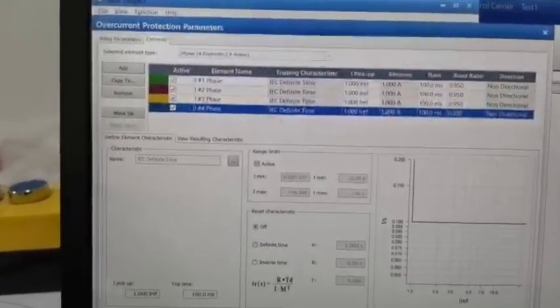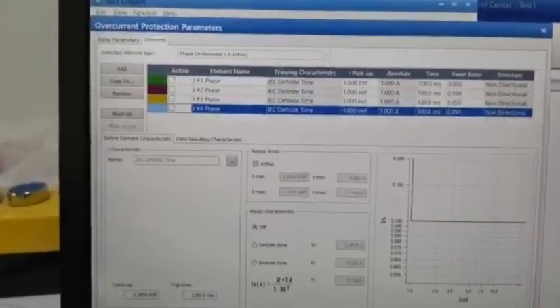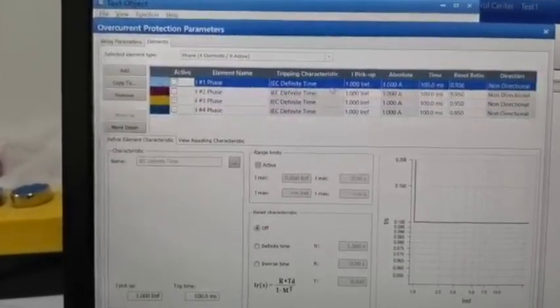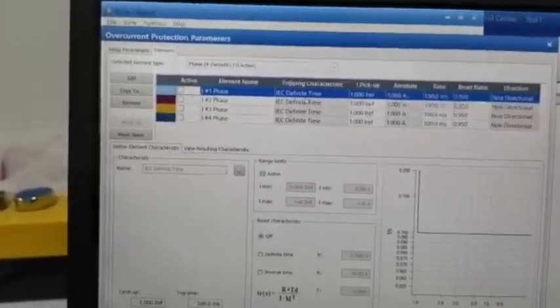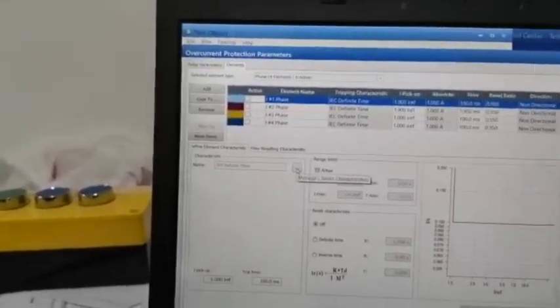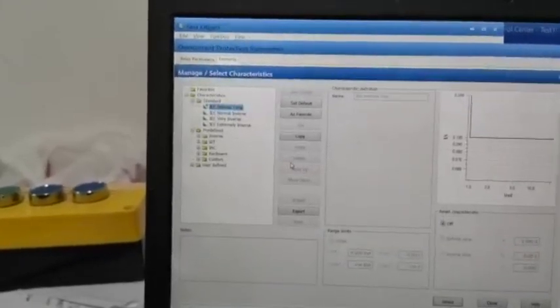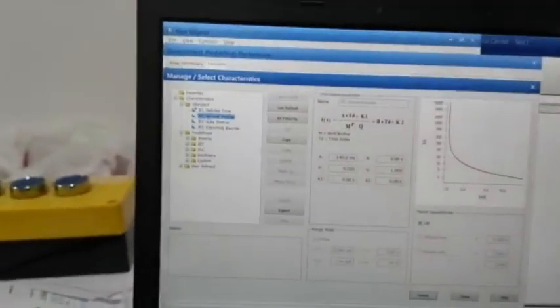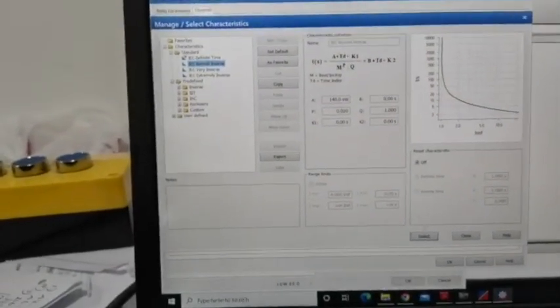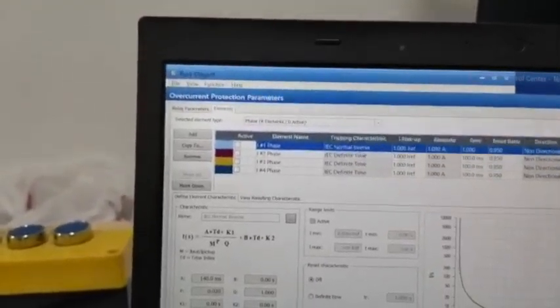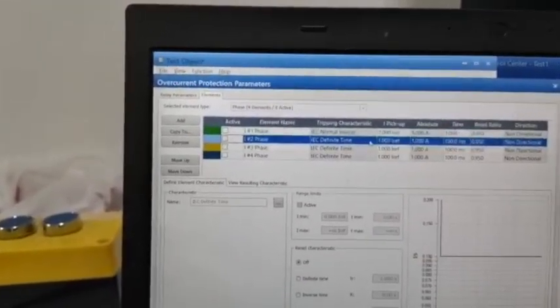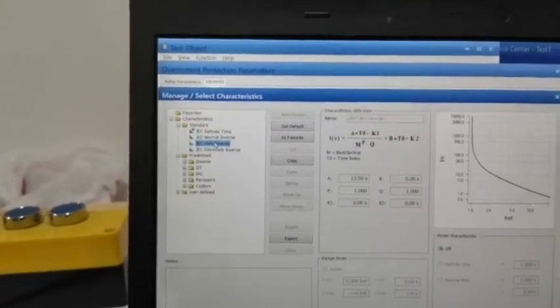You can select the curve type. For example, normal inverse. To select it, just click here and you can see the k parameters. Then you can select and it will change to normal inverse, or you can change to any other curve like very inverse.